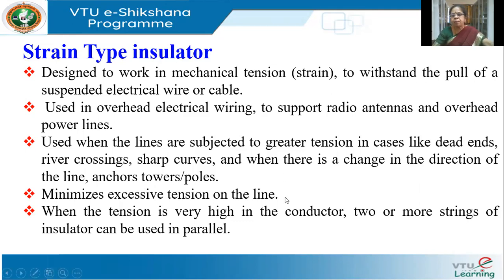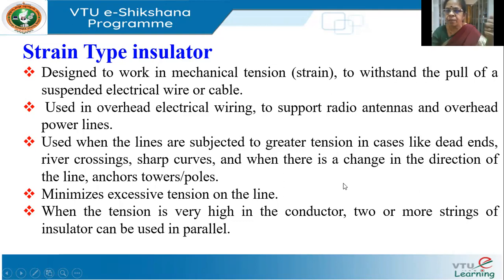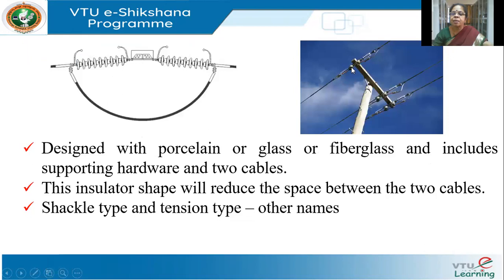Strain insulators are used to minimize tension. When we discussed sag and tension, we saw that tension is one parameter which may damage the conductor. This will minimize excessive tension on the line. When the tension is very high in the conductor, we can use two or more strings in parallel. It is designed with porcelain, glass, or fiberglass, and includes the supporting hardware and the two cables to join it. The other names for this are shackle type and tension type.